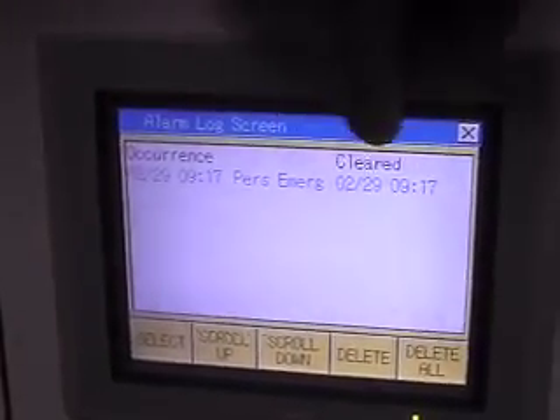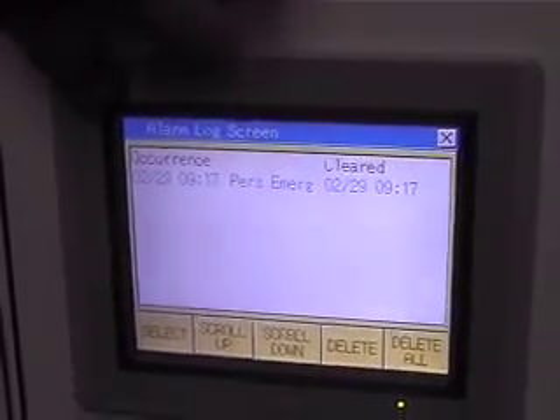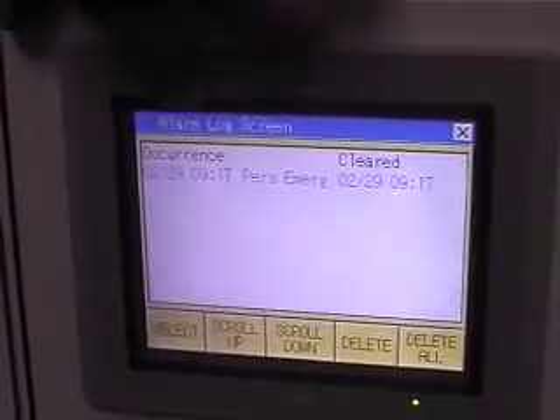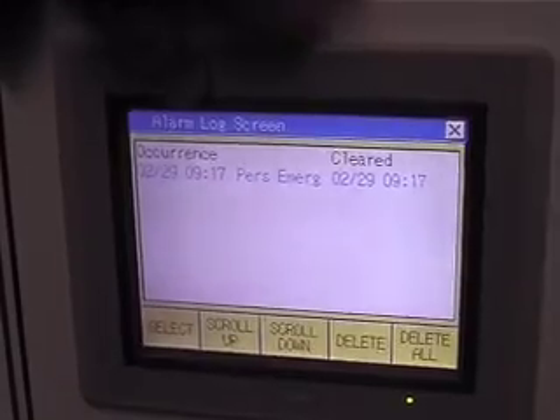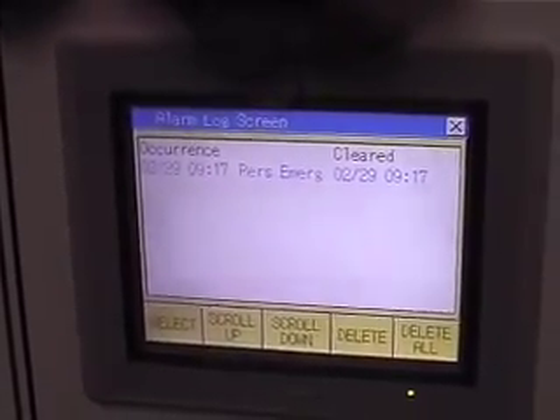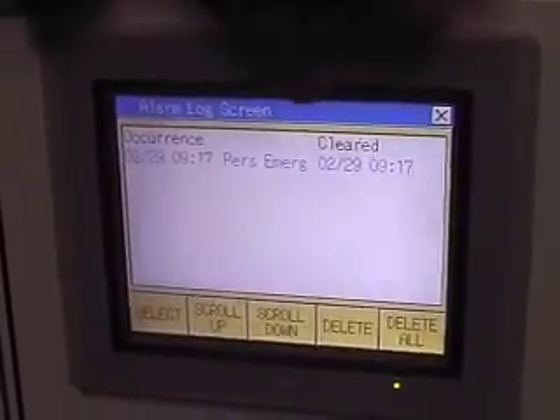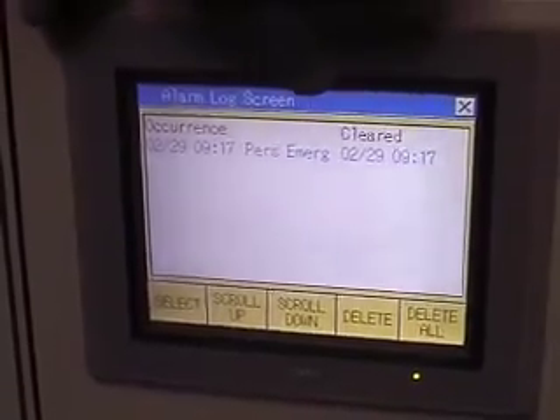You can also tell because underneath the cleared there's some writing. It gives you the month, the day, and the time that it actually occurred, and what the occurrence was, in this case personal emergency. Then when it cleared, we pulled it pretty quickly, so about in the same time frame, that thing came back out of alarm.